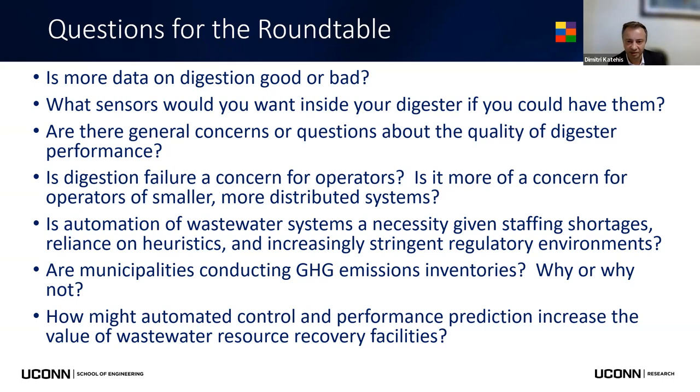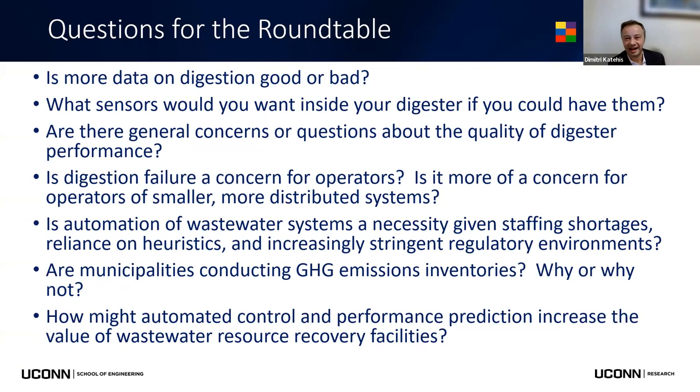Now, on the other extreme, when you're operating digesters under heavy loadings or are exposing them to variable loadings or relatively low SRTs, then you can get swings, and you do need to have your early warning system in. And that early warning system is typically going to be, frankly, pH levels and changes in pH levels, assuming everything else is consistent.